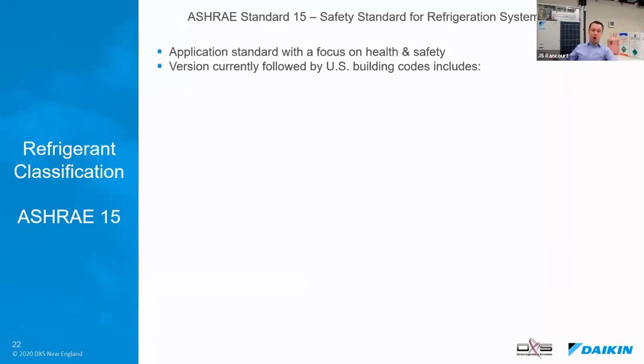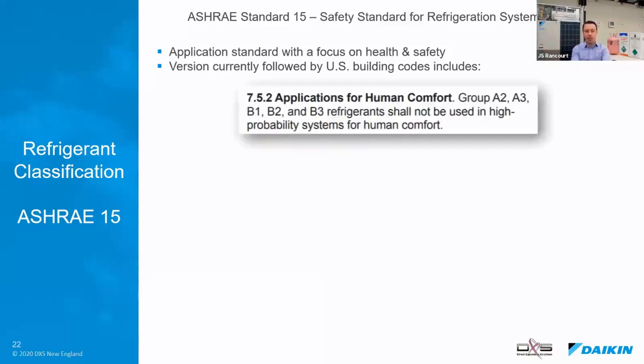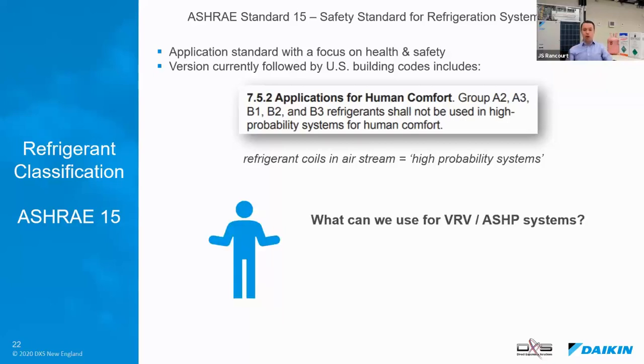The first thing is, in all the versions currently in any building codes in US and Canada, there's the famous clause 7.5.2, which basically says if you're going to put a refrigerant in the building, like a VRV system, a water source heat pump, that refrigerant is cooling or heating air, that coil in there has refrigerant, it's called a high probability system. If you're going to do that, you can't use an A2, an A3, a B1, a B2, or a B3. Great. What does that mean? What are we left with then for VRV and water source heat pumps today in buildings? Up to today, we're left with needing to use an A1 refrigerant. That is still what we're limited by due to building codes today.